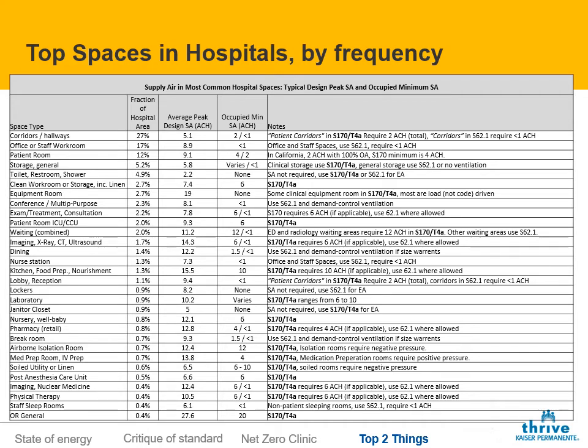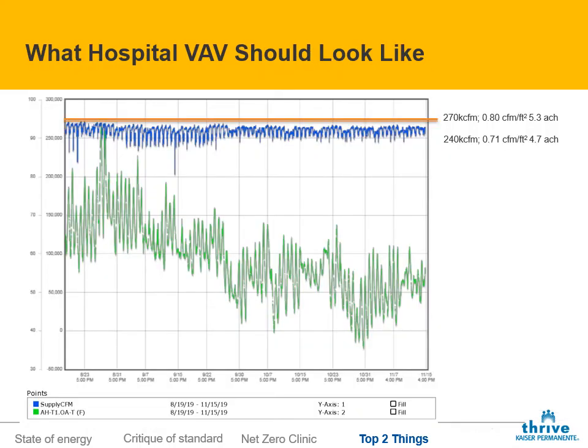So you're hearing me say these numbers, 60% turn down opportunity, 90% turn down opportunity, 80% turn down opportunity, right? Where the chart that I showed you before, we're only turning down 4%, right? Let's get back to this chart, all right? So my database has also allowed me to do some code analysis. What would the average code minimum actually be at different times of day? So let's start off.